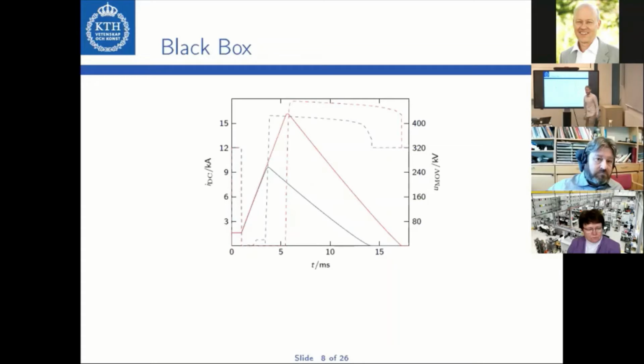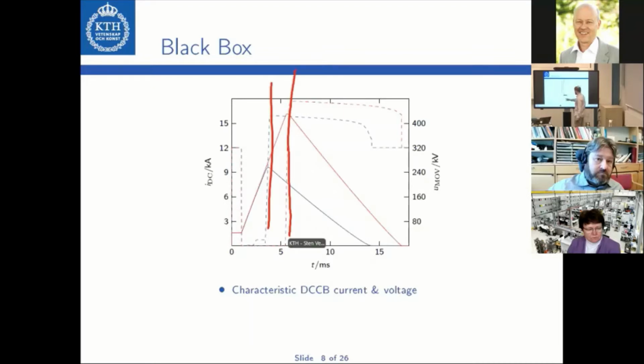An interesting aspect is that the DC circuit breaker current and voltages, as seen from the terminals of the DCCB, have a characteristic shape. You can see this in this plot. The triangular shape corresponds to the current, and the dashed lines correspond to the respective inserted counter voltage. As you can see, the shape is very similar in both cases. The only thing that differs is when the counter voltage is inserted, and this is caused by a concept-dependent internal commutation delay.